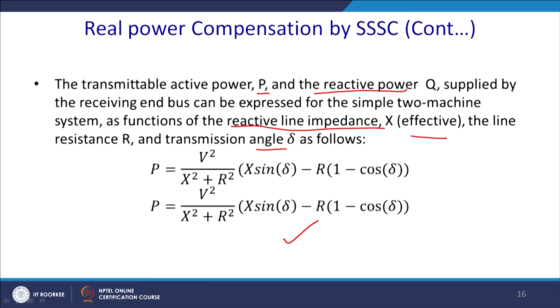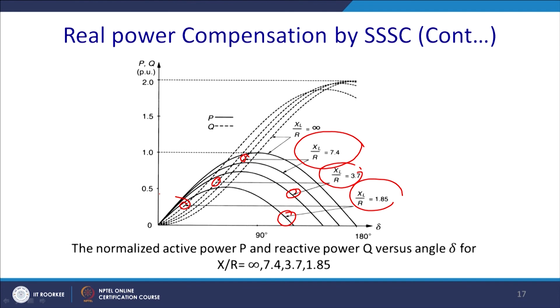So, this is the uncompensated line where the XL by R ratio is around 7.4. But when this ratio changes in a compensated line, then this is the case for the line having XL by R ratio equal to 3.7. Similarly, this is the curve for the line with XL by R ratio equal to 1.85. So, you can see that the power changes drastically, and thus if you can make this work properly with compensation, it will go to this point having XL by R ratio 7.4, and it will be shifting in this direction, and similarly it will be shifting further here. So, what happened? The real power compensation capability drastically decreases, and this is the case where the XL by R ratio is very high. So, this is actually the ideal case where the two machine theory will hold good.